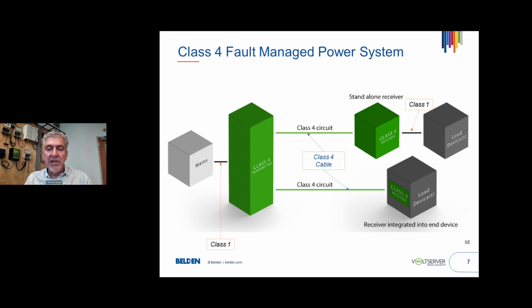As the diagram is pointing out, there's a class 1 output here shown on the upper right of the diagram, but it could very well be a class 2 circuit too, that the receiver could combine power conversion so that its output is again class 2, or it could be an inverter that turns it back into an AC output.